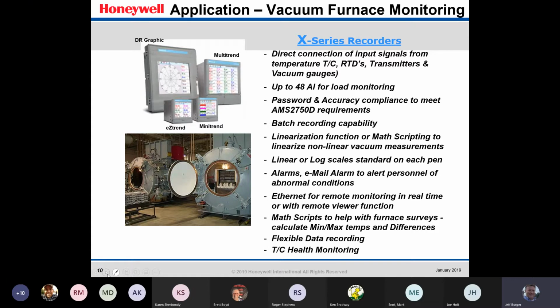Customers want to know that the furnace meets all the uniformity requirements, and they usually put a survey rack inside of these furnaces with up to 9+ thermocouples spread out through the furnace, and then produces a temperature uniformity survey report that shows that the furnace meets all the uniformity standards.